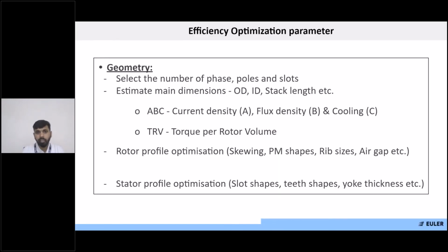First, I will talk about the efficiency optimization parameters in terms of design: how you are selecting the geometry, meaning number of phases, number of poles, slots per pole, and all the main dimensions, which depend on ABC factors, that is, current density, flux density, and cooling. If you are using natural cooling, your current density will be around 4 amperes per mm square area. If you optimize your cooling system, like using a cooling jacket, you can increase the current density from 4 to 20. These are the most important parameters to select your OD, ID, stack length, etc.